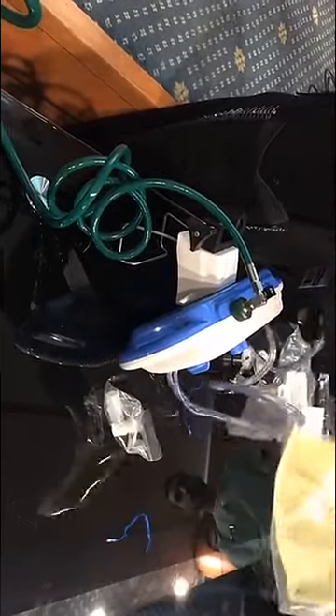By occluding the device, I should watch the pressure. It should be more than 15, not exceeding 30. And the pressure gauge. Do you guys see on the pressure gauge, ladies? Do you see? It should be more than 15, not exceeding 30. Okay, I made sure now that my machine is working. I should make sure that my pressure, again, is more than 15, not exceeding 30. Okay, in case I have a nebulization treatment, I should be able to visualize the mist coming out of this nebulizer.